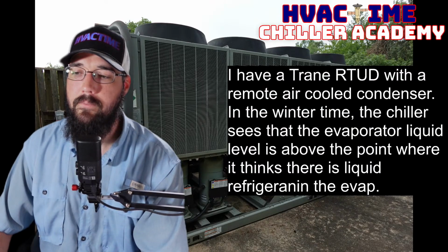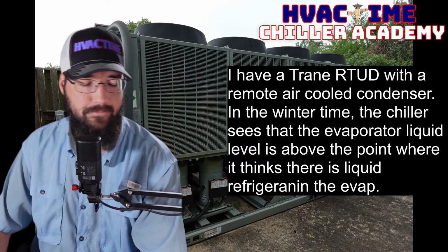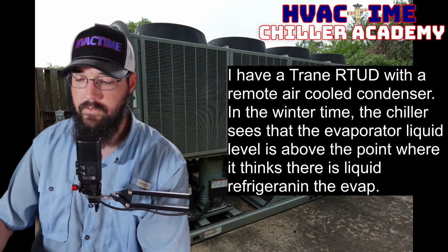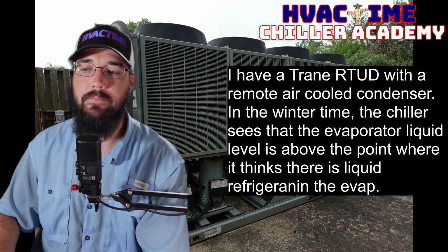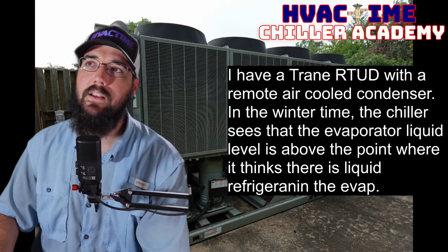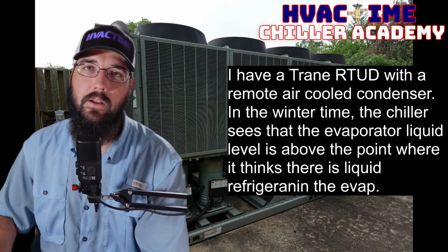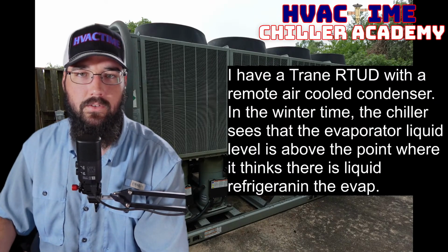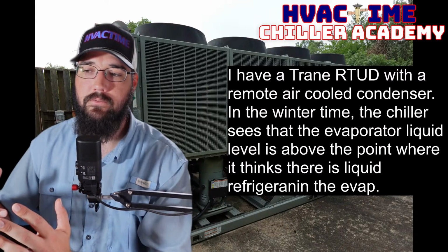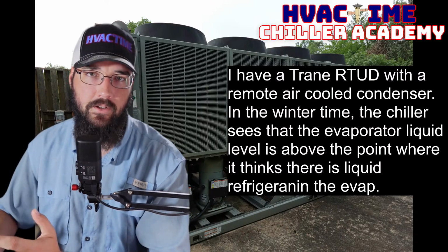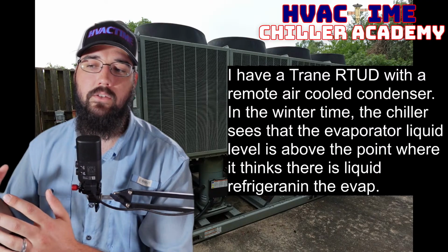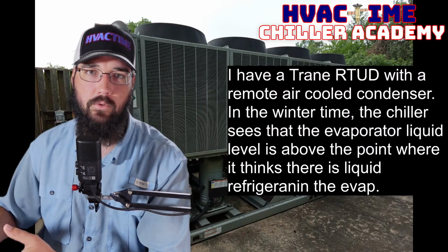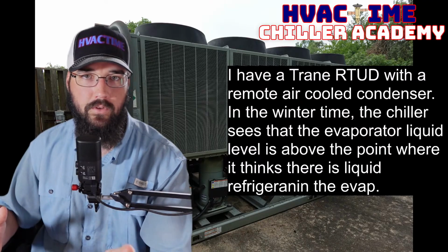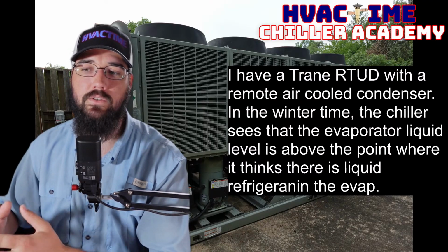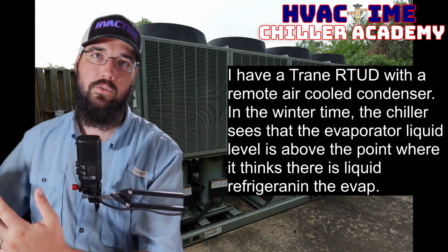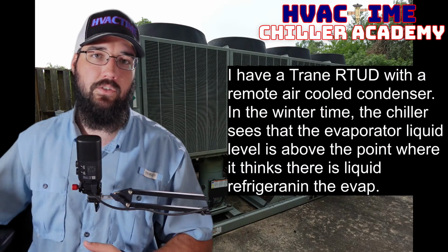Okay, so at that point, then it's a runtime issue. Absolutely. You're gonna lose a portion of your oil at startup regardless. Just as part of the compressor turning on and coming into operation, you're gonna lose a part of that just from that process alone. It's not a major amount, but you do this enough times over a span of time, you will start to migrate just from the constant starting.